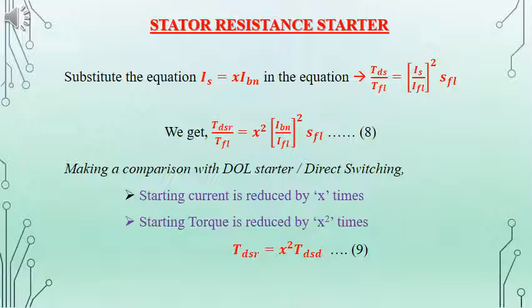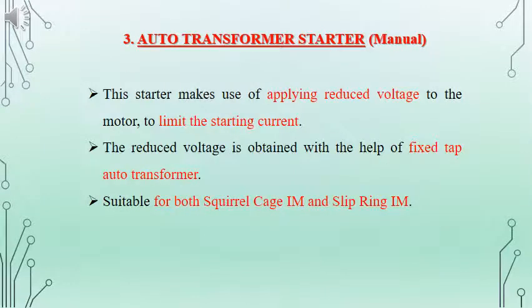That is, the torque that is produced at starting in the case of stator resistance starter will be x square times that of the starting torque that we had in the case of DOL starter. Here we can see the starting current is reduced by x times and the starting torque is reduced by x square times. In the next type of starter, that is auto transformer starter, we will be applying a reduced voltage by which we can limit the starting current.